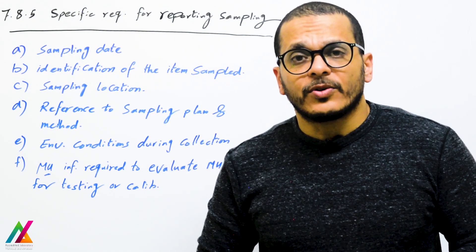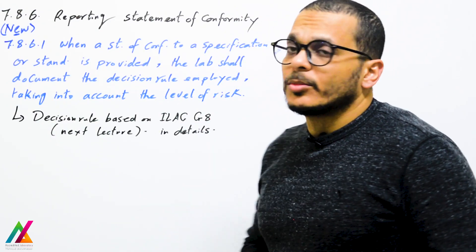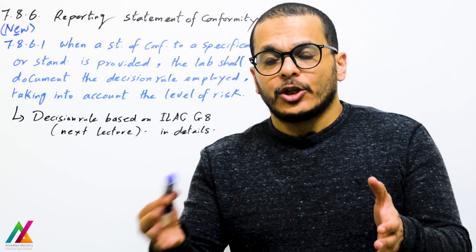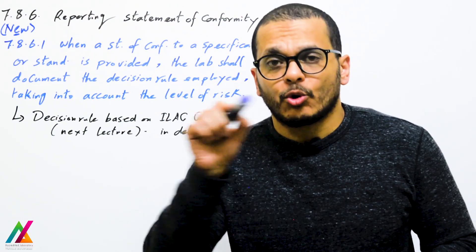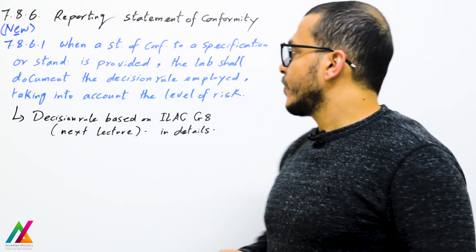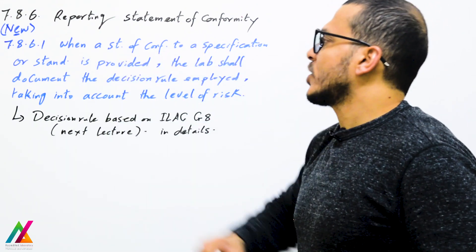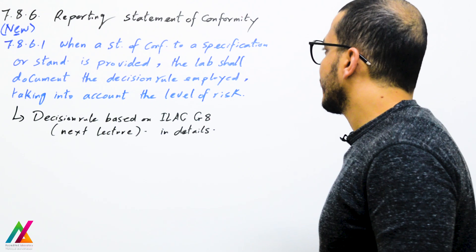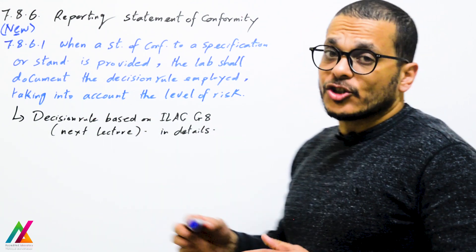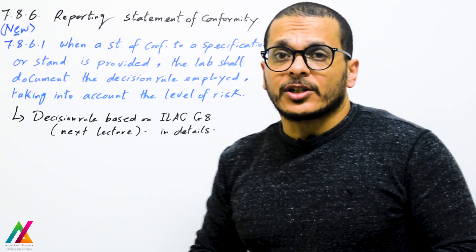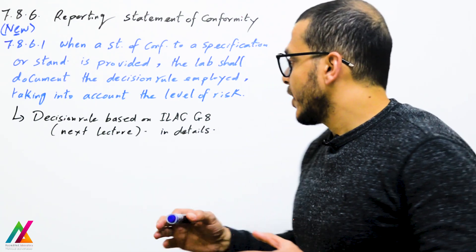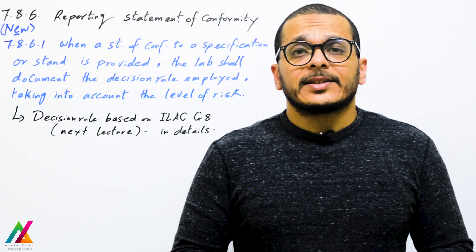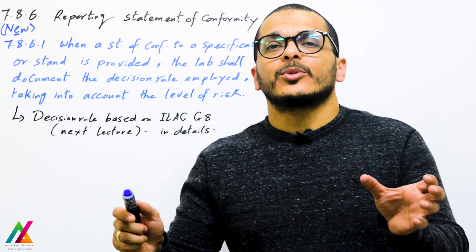A new clause added to this edition is clause 7.8.6 — reporting statement of conformity. This covers whether a sample is accepted or rejected according to a specification or standard. When a statement of conformity to a specification or standard is provided in the report, the lab shall document the decision rule employed, taking into account the level of risk. The next lecture will have a dedicated session on decision rules in detail, based on ILAC G8.